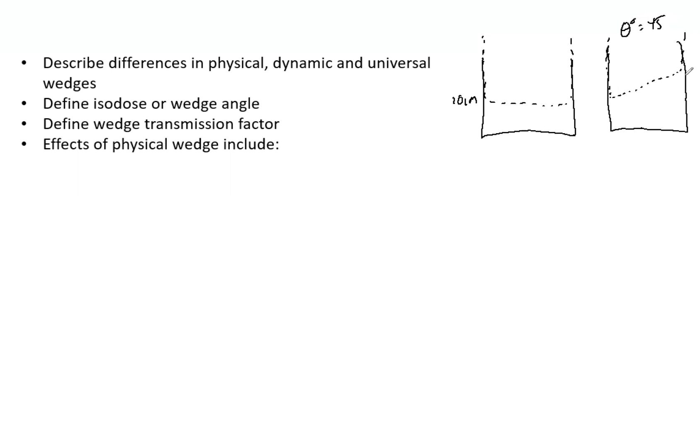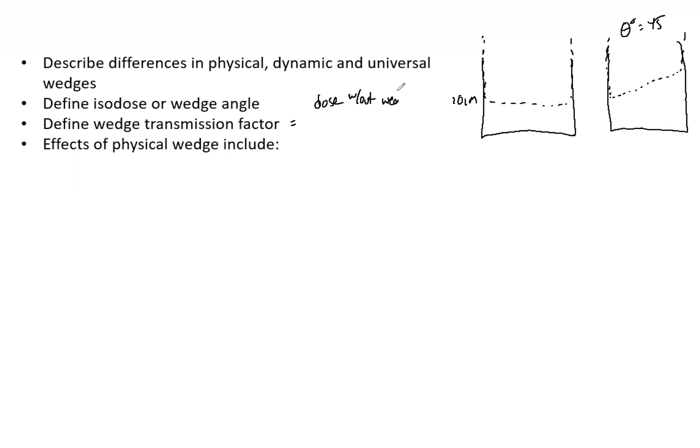The wedge transmission factor: wedges will decrease the output of the machine because they are attenuating some of the beam, so that must be taken into account. The wedge factor is the dose with the wedge divided by the dose without the wedge.